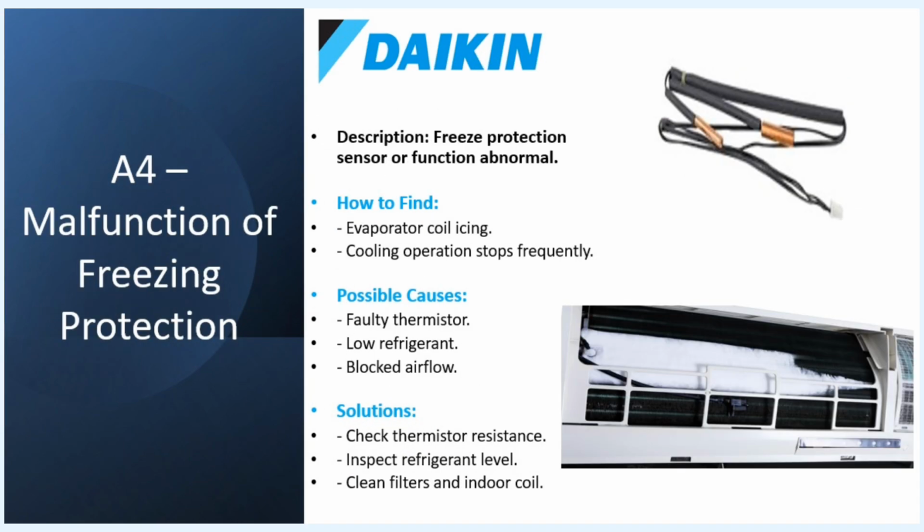A4. That's a malfunction of freezing protection. If your evaporator coil is icing up, look at the thermistor, refrigerant level, and make sure your filters and coil are clean. Fix what's faulty and you're good.